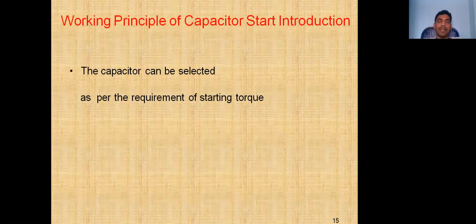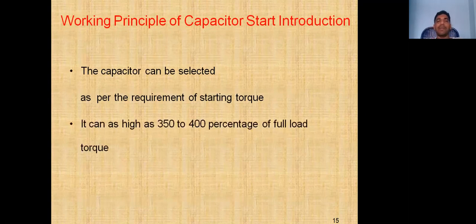The capacitor can be selected as per the requirement of starting torque. It can be as high as 350 to 400 percent of full load torque.